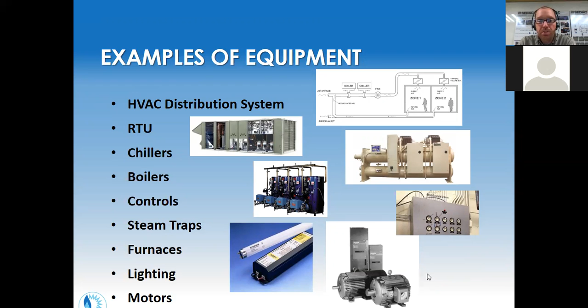Top 10 strategies for libraries specifically that we've come across: upgrade lighting and existing lighting controls, evaluate humidification needs - libraries specifically tend to be built with humidification sometimes, and that's not always necessary - use programmable thermostat setbacks during hours of operation that aren't needed, use computer power management (think of all the computers on in libraries with screens just running idle), install vending occupancy controls if there are vending machines, and use demand control ventilation, varying the amount of ventilation based on occupancy level.